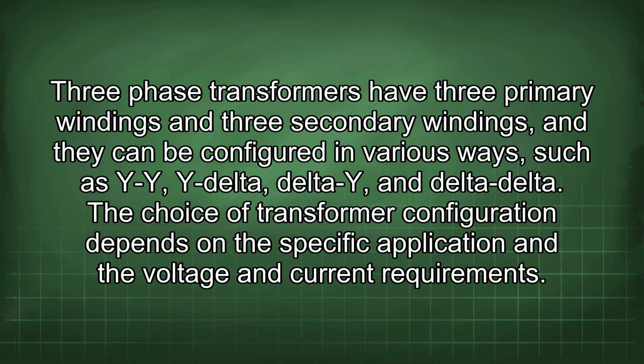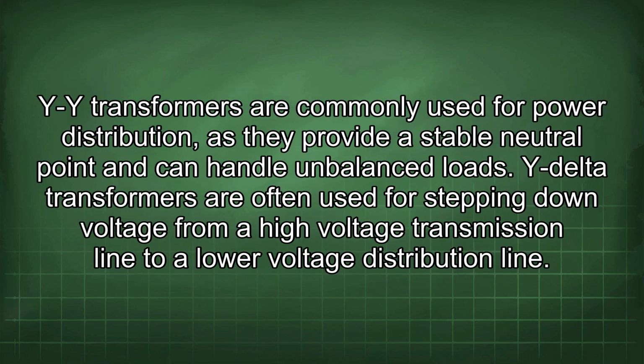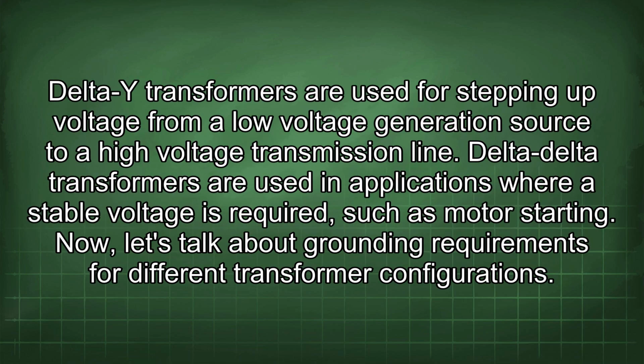The choice of transformer configuration depends on the specific application and the voltage and current requirements. Y-Y transformers are commonly used for power distribution, as they provide a stable neutral point and can handle unbalanced loads. Y-delta transformers are often used for stepping down voltage from a high voltage transmission line to a lower voltage distribution line. Delta-Y transformers are used for stepping up voltage from a low voltage generation source to a high voltage transmission line. Delta-delta transformers are used in applications where a stable voltage is required, such as motor starting.